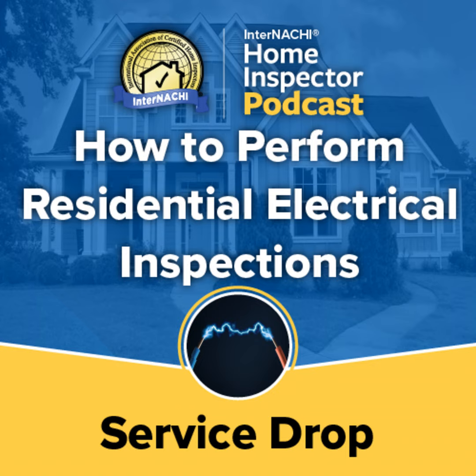Service drop. The service drop is the overhead service conductors located between the utility electric supply system and the service point. The service point is the point of connection between the facilities of the service utility and the wiring at the house. The point of attachment of the overhead service conductors to a building or other structure should be not less than 10 feet or 3,048 millimeters above the finished grade.